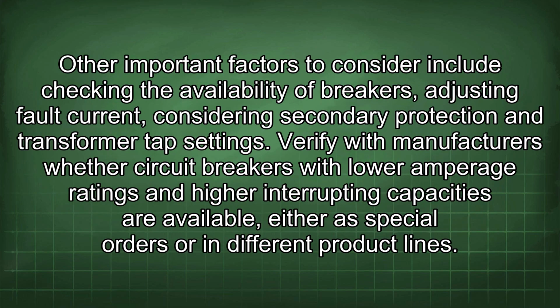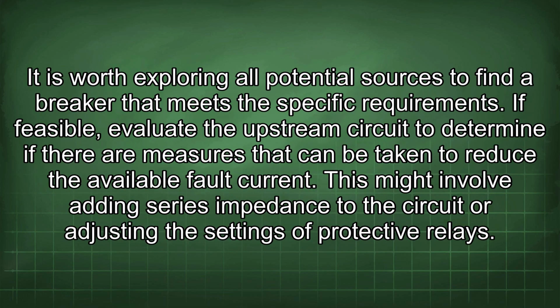Other important factors to consider include checking the availability of breakers, adjusting fault current, considering secondary protection and transformer tap settings. Verify with manufacturers whether circuit breakers with lower amperage ratings and higher interrupting capacities are available, either as special orders or in different product lines. It is worth exploring all potential sources to find a breaker that meets the specific requirements.